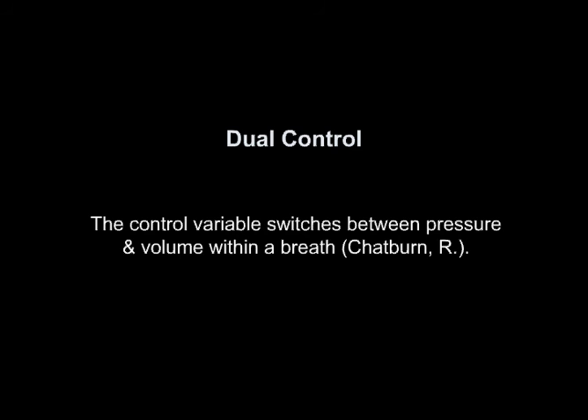With dual control, the control variable switches between pressure and volume within the same breath. Two examples of this are the Pmax mode on Dräger Evita-series ventilators — very popular in their Apollo anesthesia machine — and VAPS, or volume assured pressure support, in BIRD machines. I'm going to demonstrate Pmax on a Dräger machine.